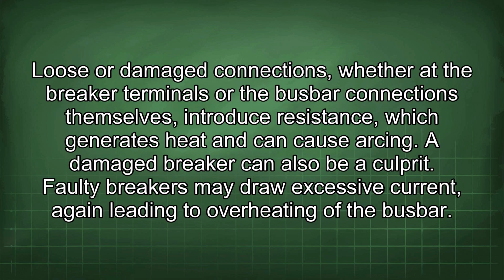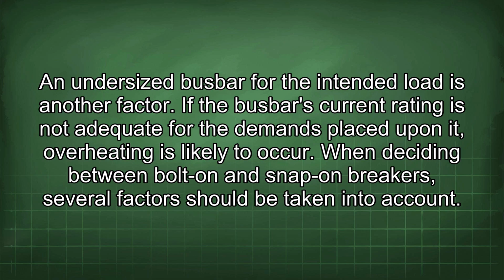Loose or damaged connections, whether at the breaker terminals or the busbar connections themselves, introduce resistance which generates heat and can cause arcing. A damaged breaker can also be a culprit. Faulty breakers may draw excessive current, again leading to overheating of the busbar. An undersized busbar for the intended load is another factor. If the busbar's current rating is not adequate for the demands placed upon it, overheating is likely to occur.